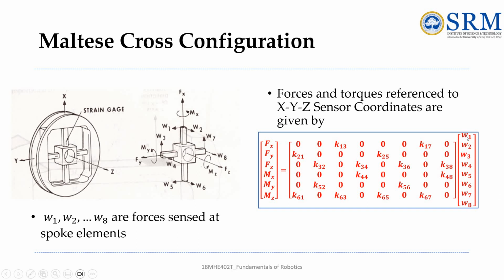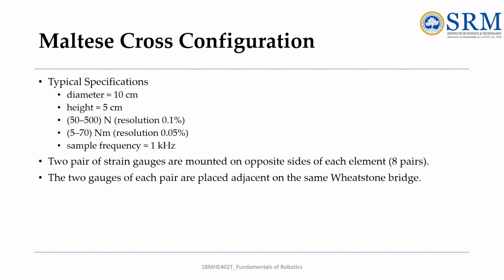Okay. And the last matrix W1 to W8. These are the forces sensed at the spoke elements. So this is how the coordinate matrices is calculated for this Maltese cross configuration. Okay. Typical specifications of this Maltese cross configuration: diameter is approximately 10 centimeter, height is approximately 5 centimeter, and it has a 50 to 500 Newton range, resolution is 0.1 percentage, and 5 to 70 Newton-meter, resolution is 0.05 percentage. Sample frequency is approximately 1 kilohertz.